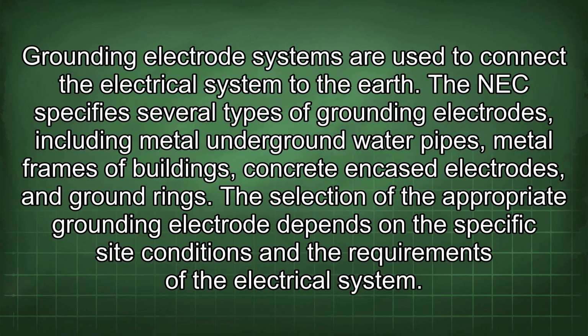Grounding electrode systems are used to connect the electrical system to the earth. The NEC specifies several types of grounding electrodes, including metal underground water pipes, metal frames of buildings, concrete encased electrodes, and ground rings. The selection of the appropriate grounding electrode depends on the specific site conditions and the requirements of the electrical system.